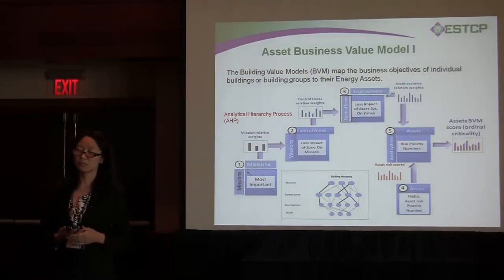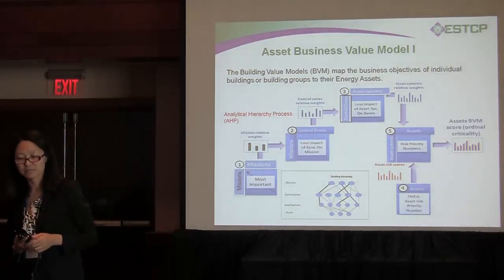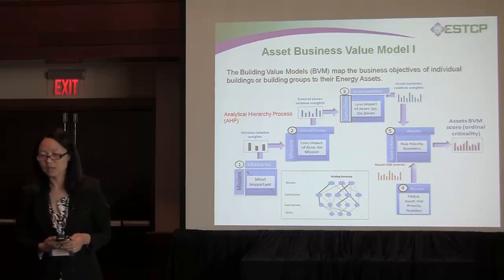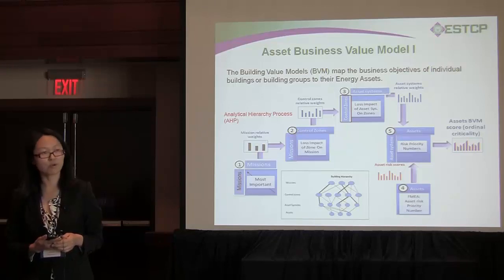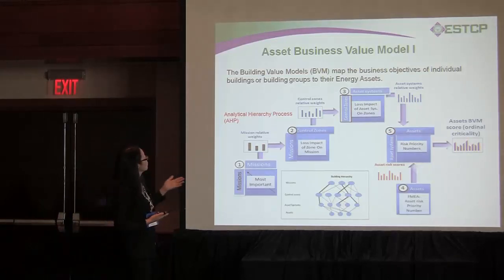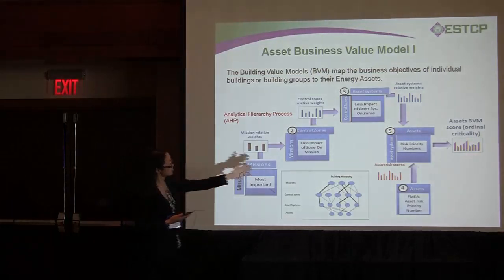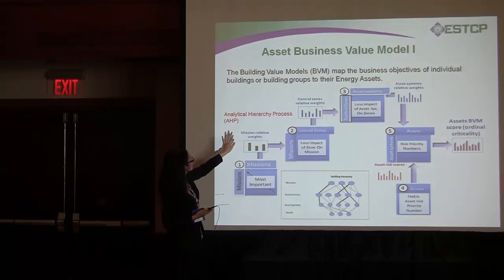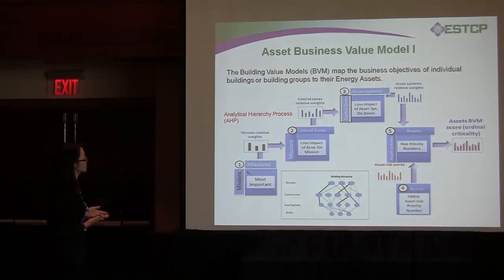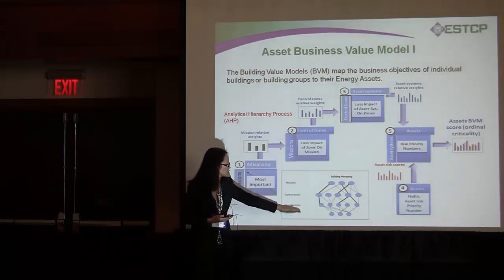Now I'll share some work done by Rutgers University on how to develop the asset business value. We have two ways to represent business value of an asset. The first is to derive the ordinal criticality of the asset — we apply an approach called the Analytical Hierarchy Process to map the building's business objectives down to the asset level. Another way we use is Failure Mode Effect Analysis, where we divide the whole system into multi-layers and map criticality from the mission layer to the asset.